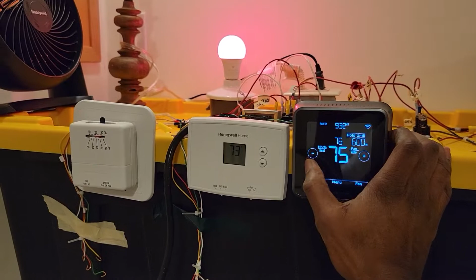Okay, so let's turn off the heat right now. I'm going to do it by lowering the temperature this time. So we're still in heat mode, and the fan is still blowing because there's a little bit of extra heat in the heat exchanger, as explained in the previous videos. That's going to go off in a second once the heating element of the sequencer cools down and disconnects that sequencer connection.